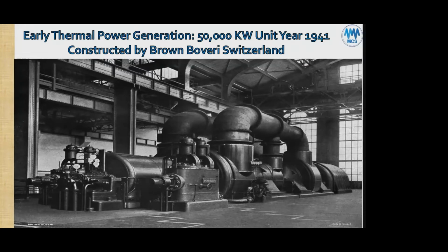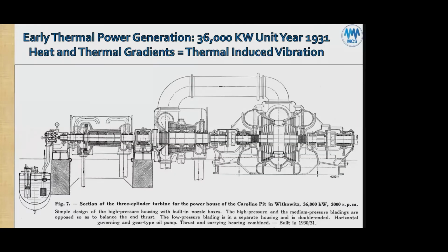So these machinery from the beginning started experiencing vibrations. Here we have a cross section from 1931 of a 36,000 kilowatt, 3,000 RPM STG unit, also produced by Brown Boveri. They obviously rely on steam at the inlet. Here we have the high pressure steam on the inlet side. Let's see if I can get this mouse going. There we have high pressure, intermediate steam pressure here, and we have an LP turbine at the end.